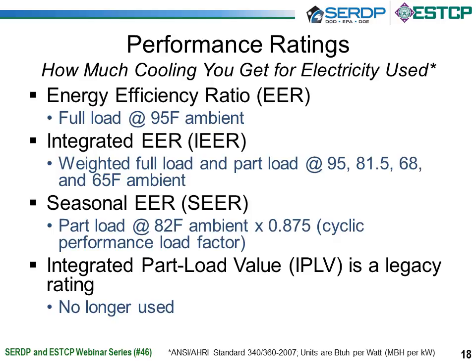There are 4 energy efficiency rating definitions that I just want to go over. These describe how energy efficient an air conditioner is. The first one is the energy efficiency ratio, the EER, and that's just at a single point. It's the efficiency at full load at 95 degrees outdoor temperature. The second one is the IEER, or integrated energy efficiency ratio. This is a weighted average of efficiency at 4 different temperatures and 4 different loads, and gives a more real-world description of what the air conditioner's efficiency will be in actual operation.